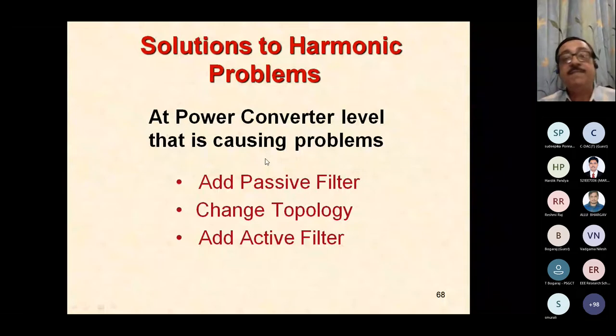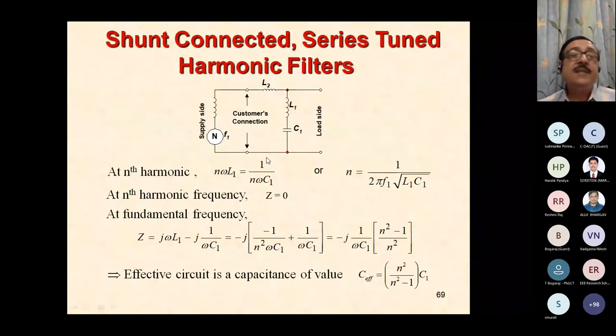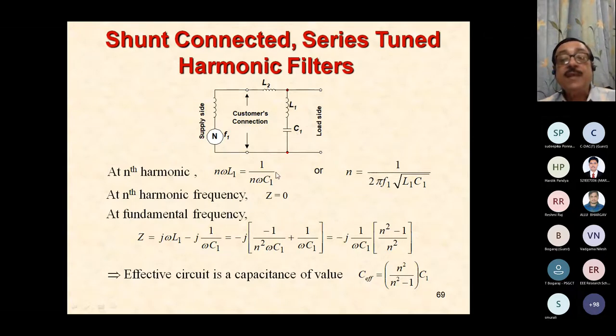So let's say we add a passive filter. This is a typical, very popular type of filter. It's a shunt connected filter, which is series tuned. So L1 and C1 are tuned to some nth harmonic, such that at the nth harmonic, the impedance is zero. And you remember that the load is creating the harmonic problem on current, not the source. The voltage was a sine wave. So now, just for the time being, forget about the existence of L2.